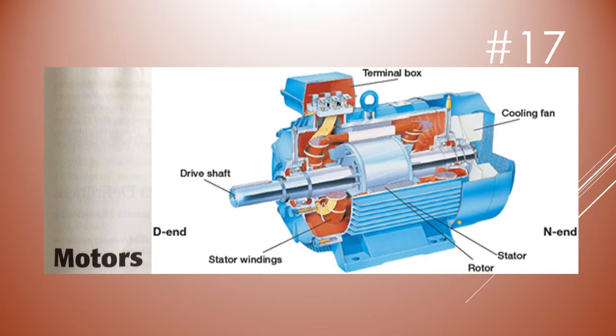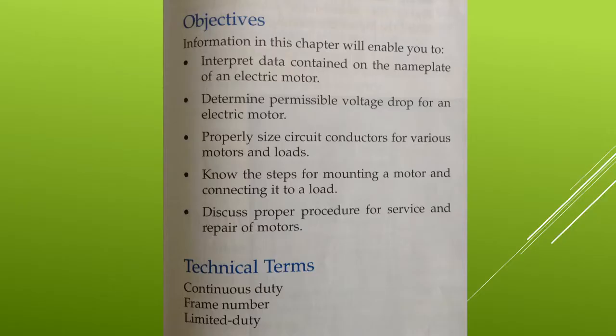Now moving on to the all-important chapter of motors, chapter 18, objectives. Interpret data contained on the nameplates of an electric motor. Determine permissible voltage drop for an electric motor, and properly size circuit conductors for various motor loads. Know the steps for mounting a motor and connecting it to a load, and discuss the proper procedure for service and repair of motors. Technical terms discussed here are continuous duty, frame number, and limited duty.